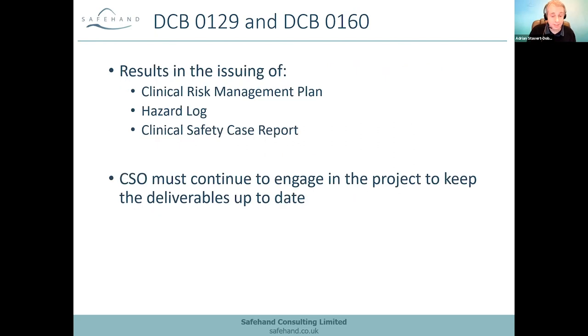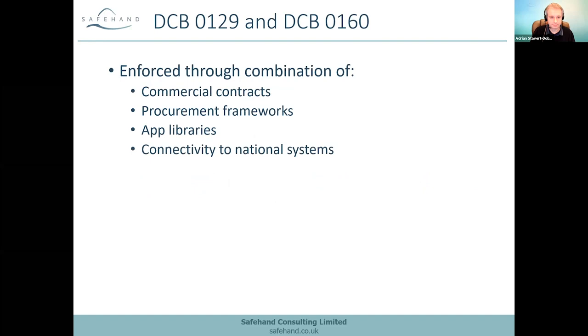So when you comply with the standard, you're obliged to create three documents: the clinical risk management plan, the hazard log, and the clinical safety case report. These deliverables are different, particularly the first and last ones, to the ones that you will see in 14971. And as we say, these documents will need to be shared with your customers. The clinical safety officer also has to keep this documentation up to date in live service of the product, so you can't just write them once. Just as with medical devices, everything has to be kept up to date in line with the product.